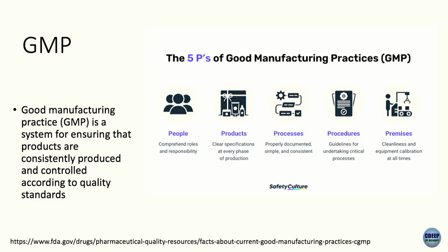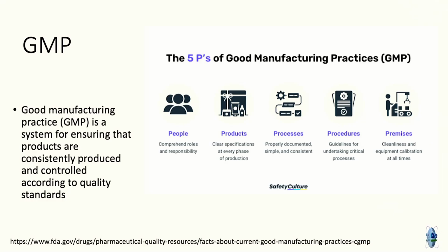And finally, and very important, where this is getting manufactured. Premises have to be tightly controlled. Cleanliness should be there. Equipment should be calibrated. Suppose, just for an example, the pipette says to add 10 microliter, right? You added 10 microliter, but the pipette is not calibrated. The pipette was calibrated 1 or 2 years ago. What will happen? Instead of 10 microliter, it may be 9, 8, 12, whatever. So you are adding variation.